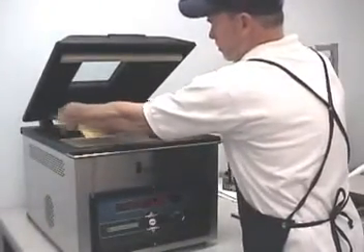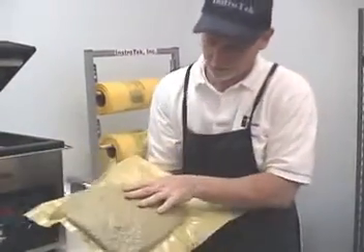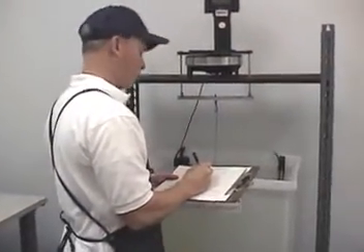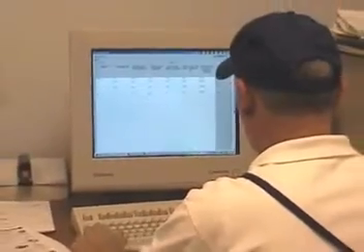The CoreLok is a vacuum pump system that uses specially designed polyurethane bags to seal samples. Once sealed, the sample is ready for testing. The lab technician simply writes down weights at different stages of the process, indicated by the data collection table, and uses the GravitySuite software to very quickly determine results.